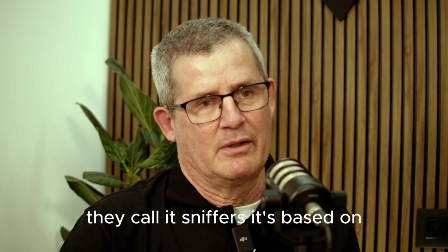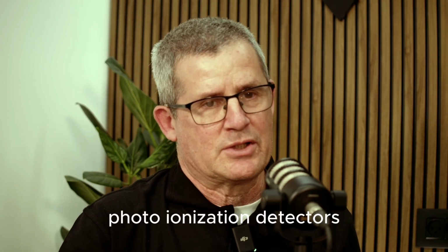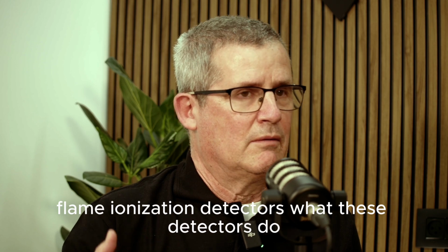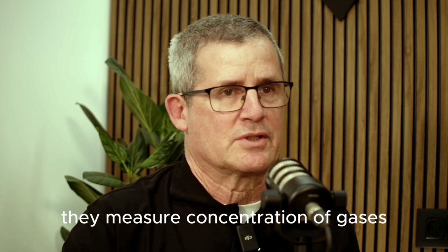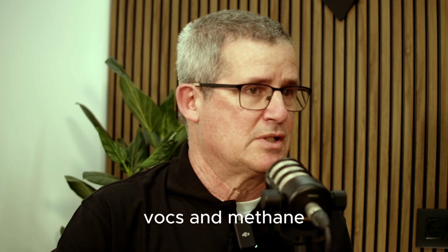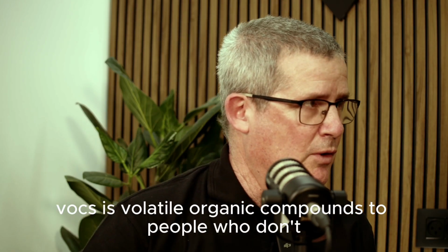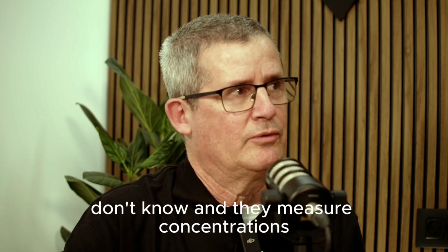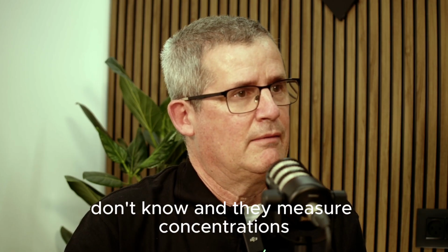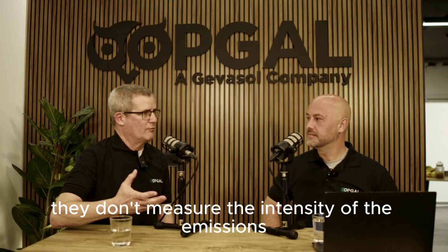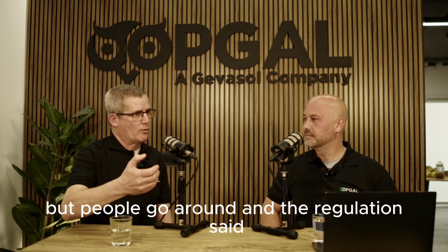It's based on photoionization detectors and flame ionization detectors. What these detectors do, they measure concentration of gases, VOCs and methane. VOCs is volatile organic compounds, for people who don't know. And they measure concentrations. They don't measure the intensity of the emissions.